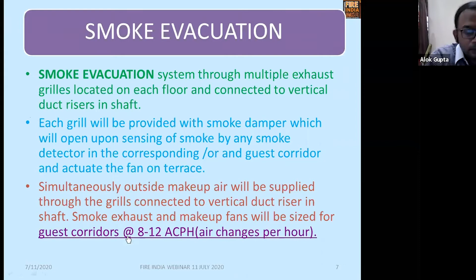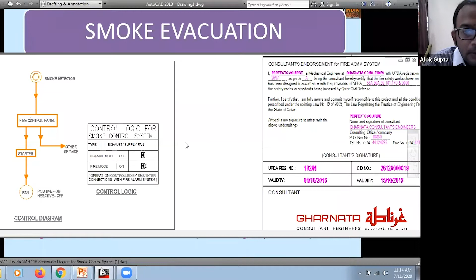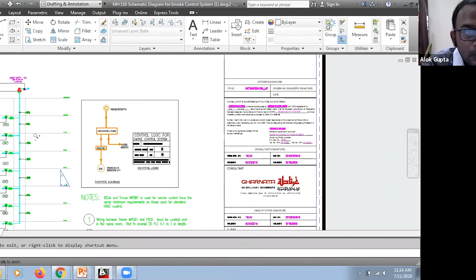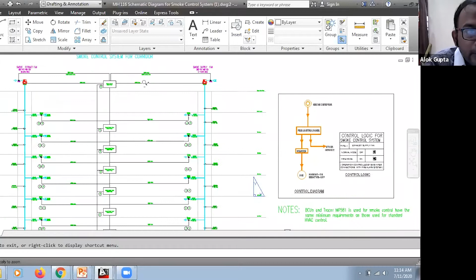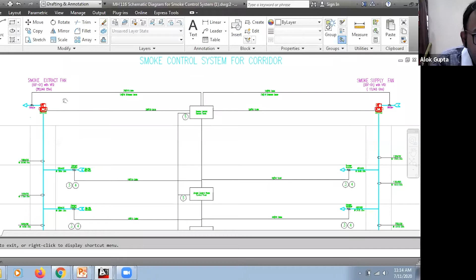So this is a typical connection. We'll see to it. If you consider this, this is how the ventilation of a building is done. For a smoke case, we keep the extraction fan slightly higher. For example, in this particular case, the exhaust air is 20,848 CFM and the supply air is 17,445. So we are exhausting more air.